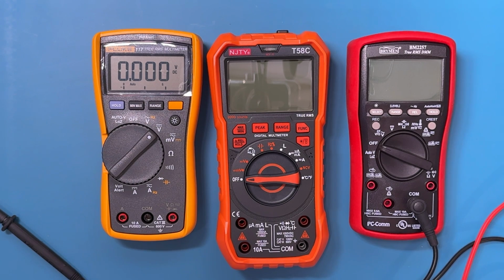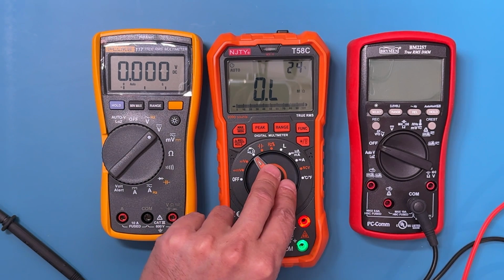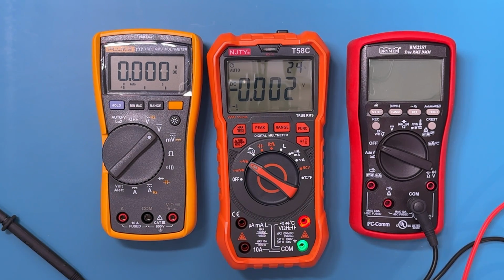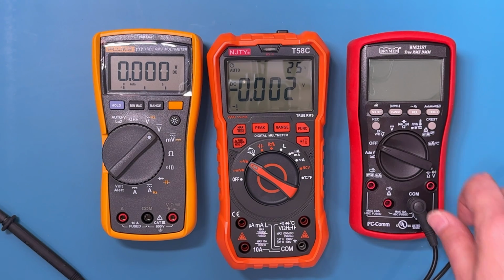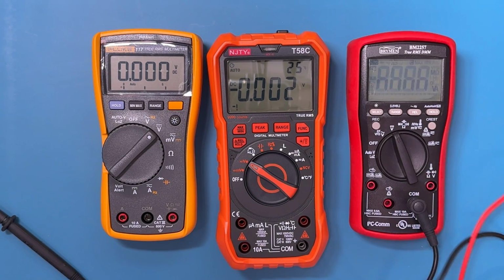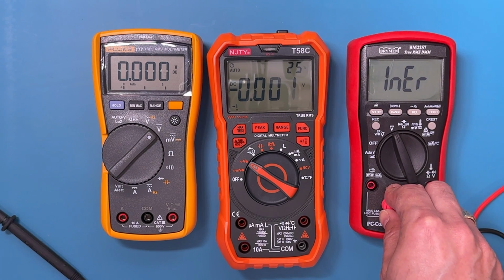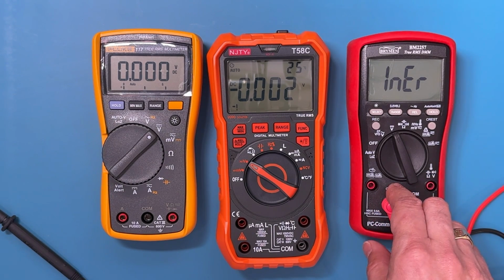Unfortunately, the message is shown briefly and you may miss it. Others light up the sockets to tell you which ones to use in a given mode. However, the lights are only present for a few seconds, and once again, you may miss it. The best solution I have seen is a warning tone and error code when the leads are connected to the wrong socket. You can't miss it.